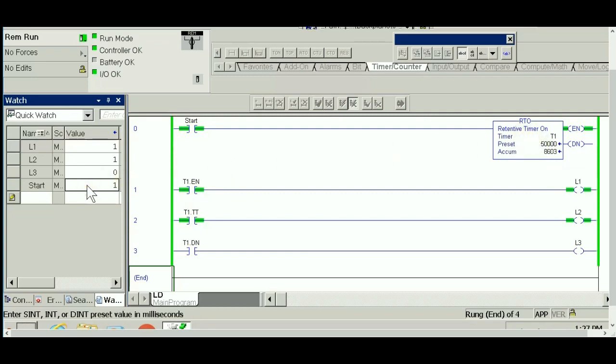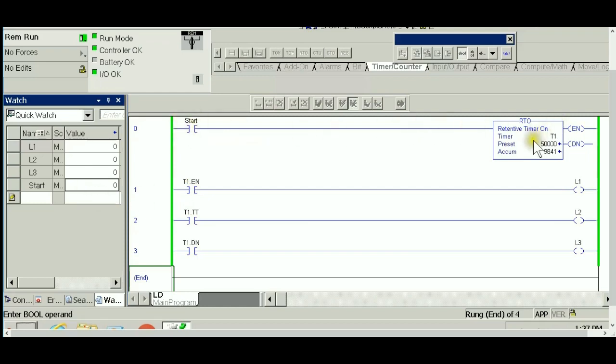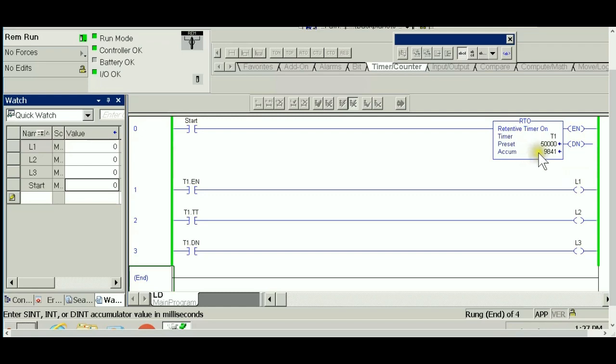Anytime I let go the start, it goes back to zero. Right now this is false, the timer is disabled. However, if you notice, the value of the accumulator is stuck at 9,000. It didn't reset it to zero as it did in the TON, and hence this is the retentive timer. Anytime you want to maintain whatever value the timer has accumulated, the RTO timer is the one to use.